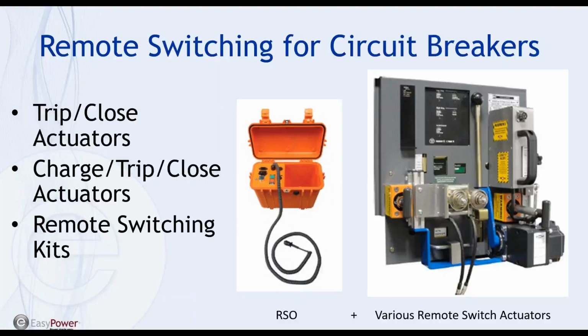So that is an option to have charge trip close as well as trip close. These are really the solenoids that push the close and trip buttons. The RSAs are operated with what we call an RSO, a remote switch operator. What's nice about this system is you can have a central control operator, the RSO, and it can connect to many different varieties of remote switch actuators.